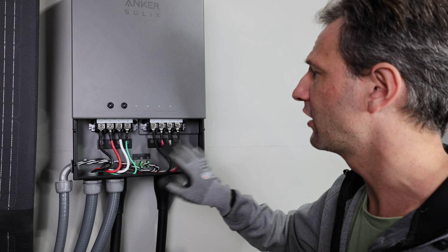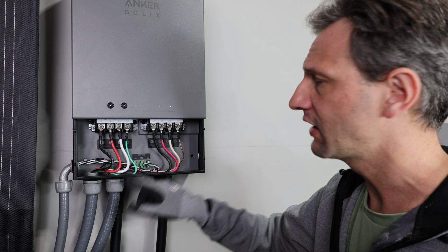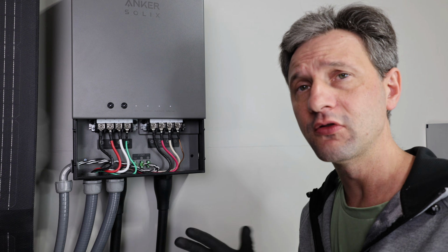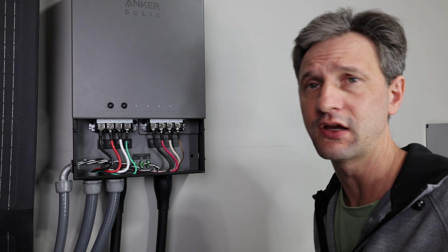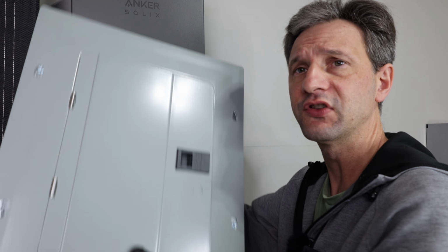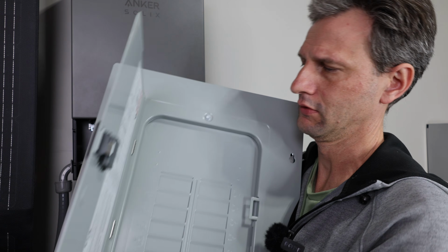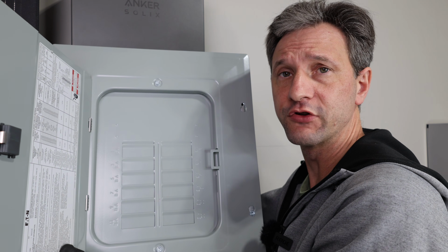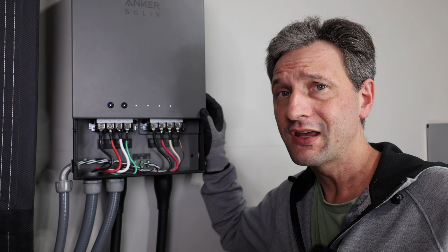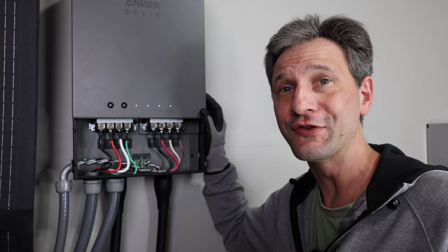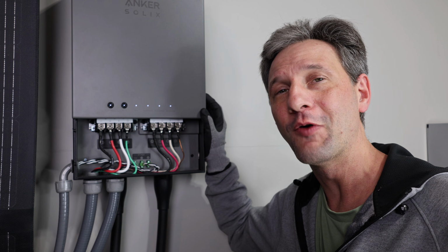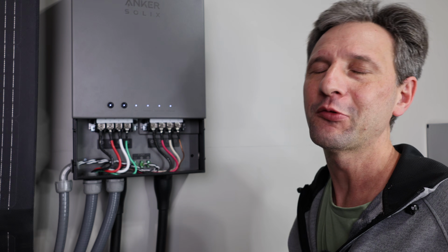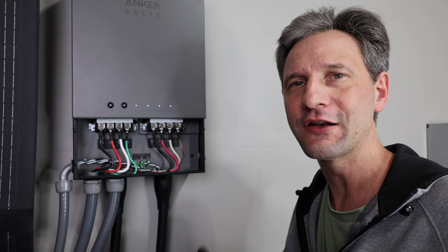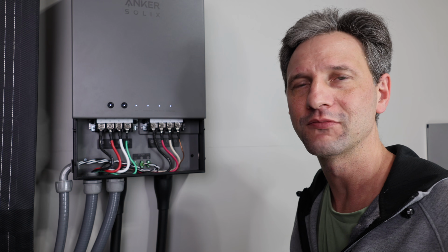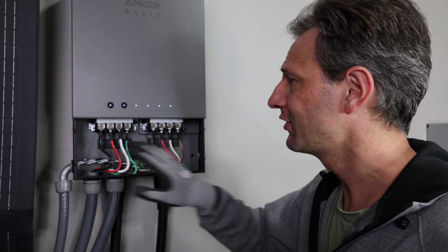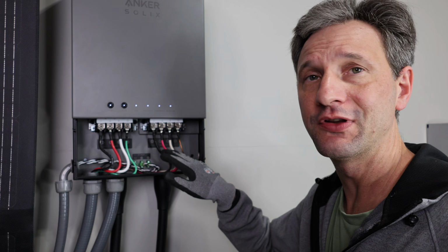Then for the output, I also use 6 gauge, and I ran that through a flexible conduit over to a sub panel, which you can get through Anker, or you can get your own. Just a simple sub panel with locations for all the emergency circuits you want to supply. In my case, I have a couple 30 amp breakers so we can run an 11 kilowatt on-demand hot water heater, but you'd probably put in a breaker for your refrigerator, some emergency circuits, security, things like that. Really easy - input from your main panel, output to your sub panel.